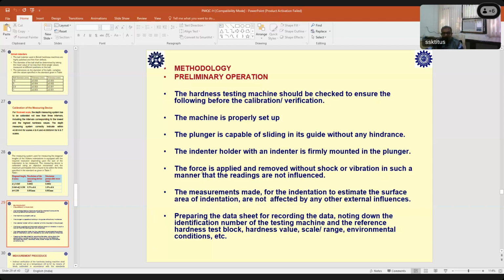So that is why the force is applied and removed without shock or vibration, in such a manner that the reading is not influenced. So these are the influencing factors. The next is the measurement. The measurement made for the indentation, to estimate the surface area of the indentation, should not be affected by any other external influences. Sometimes, whenever you are making a measurement on the hardness block, most hardness blocks, just to protect them, have oil applied to keep them from rusting and other things.